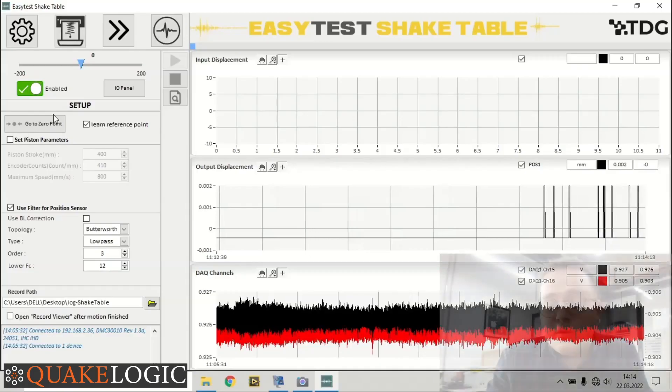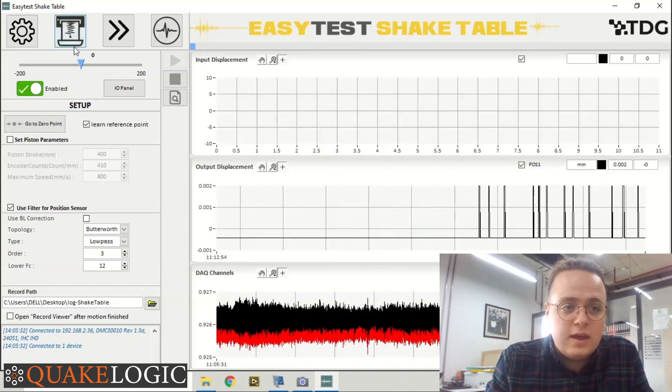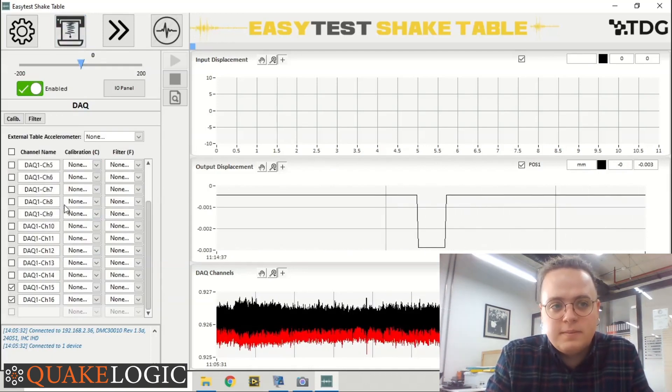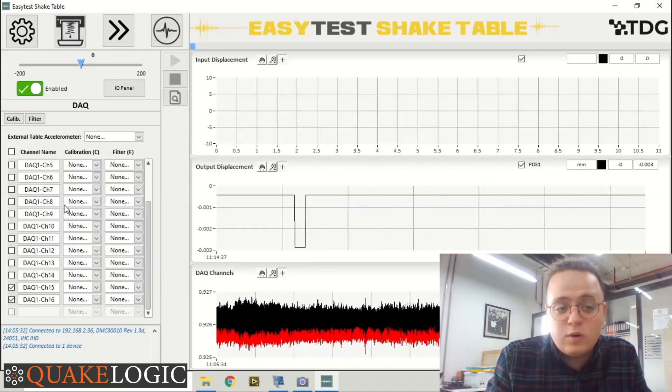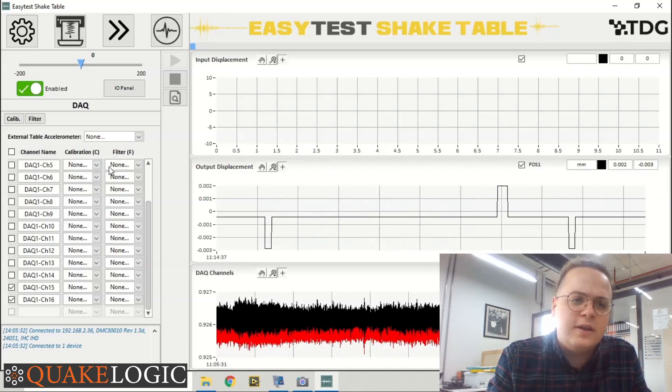In order to configure the data acquisition device, you may click on the second window and the table for all the channels of the data acquisition device will appear. By using this table we can calibrate or filter each channel of the data acquisition device separately.